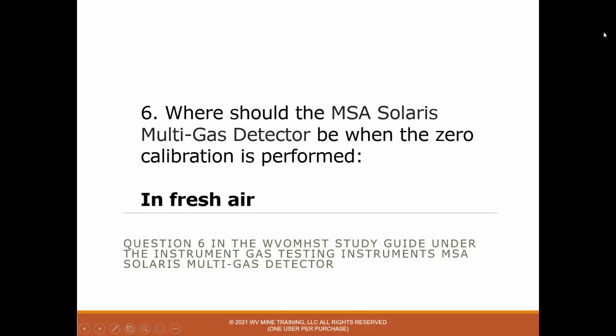Number 6, where should the MSA Solaris multi-gas detector be when the electrical zero calibration is performed? And the answer to that is in fresh air. So when you perform this zero calibration, it's going to set itself to read 0% methane, 20.8% oxygen, and 0 parts per million carbon monoxide. So you need to be in an environment where you know that you have 0% methane, 20.8% oxygen, 0 parts per million carbon monoxide. So you always want to be in fresh air when doing the zero calibration.